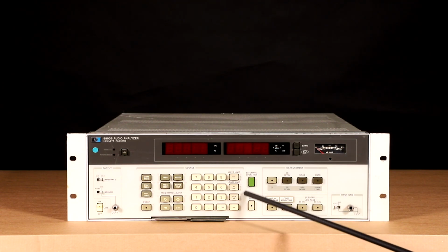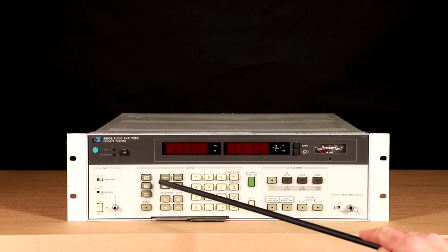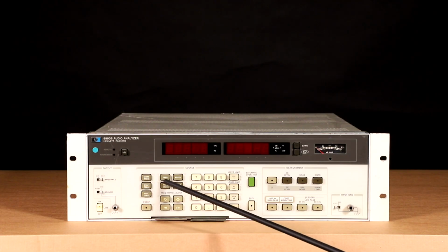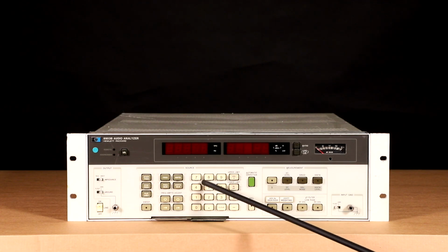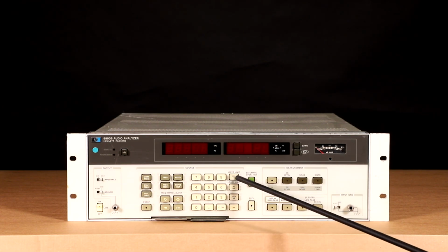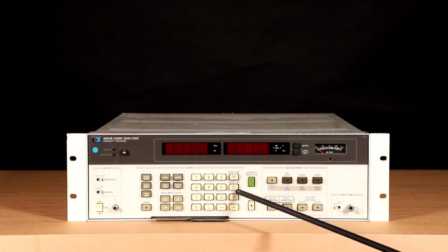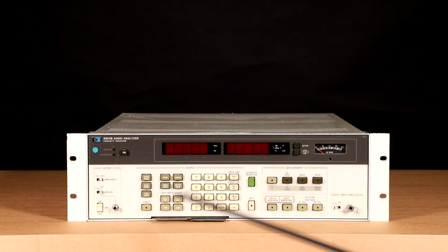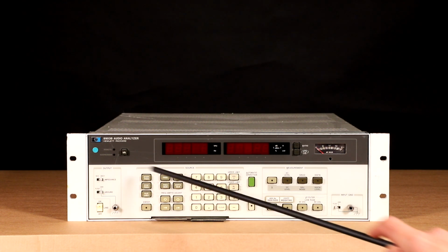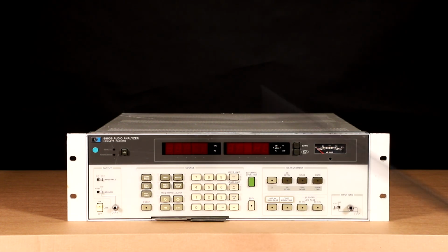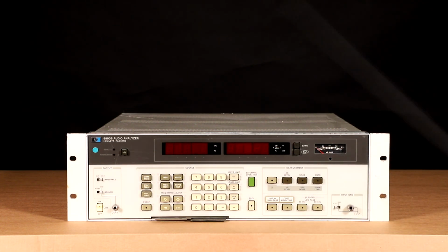Over here, this is like a source unit. Here you can set up the frequency increment and amplitude increment, or you can just type the frequency right here. If you type a frequency and hit this button, it's going to be in kilohertz, this is in hertz or millivolts, and this is in dB or dBm. There are still a lot of things I do not understand about this unit. But I tried some things already, and I know this thing is operational, and it was claimed as operational.